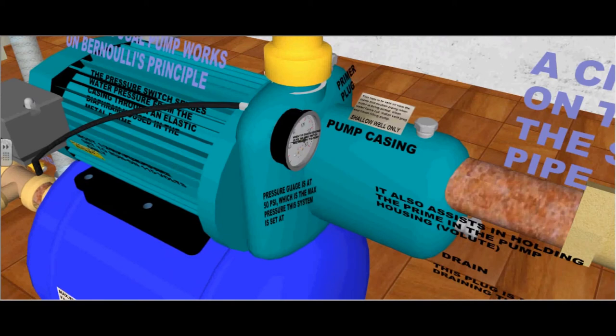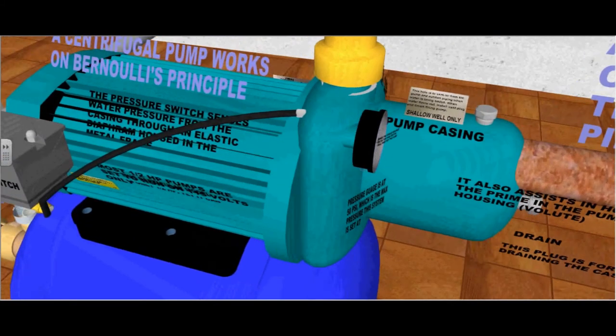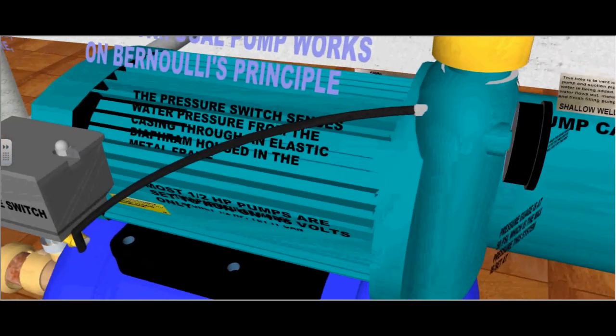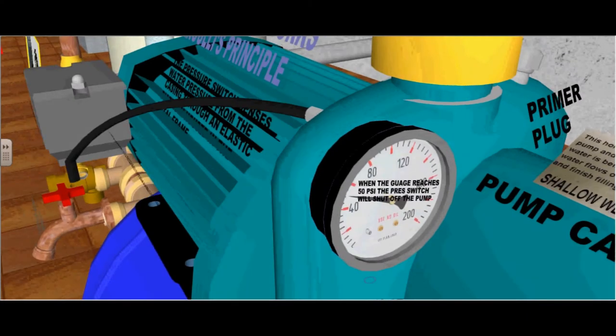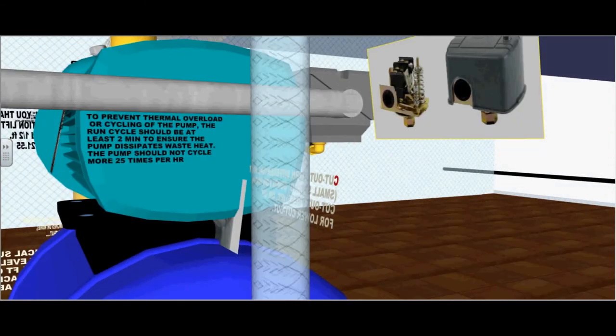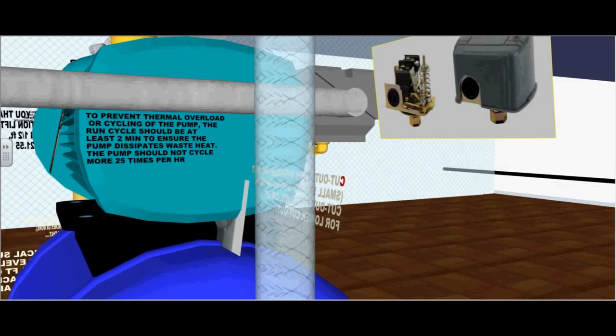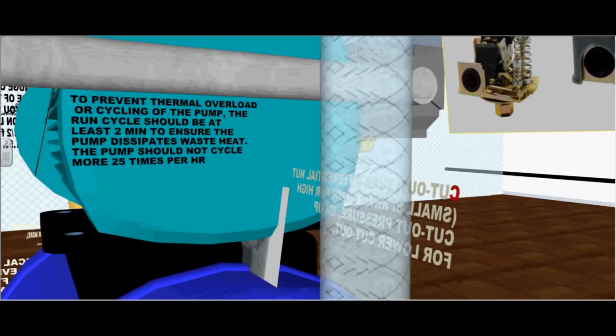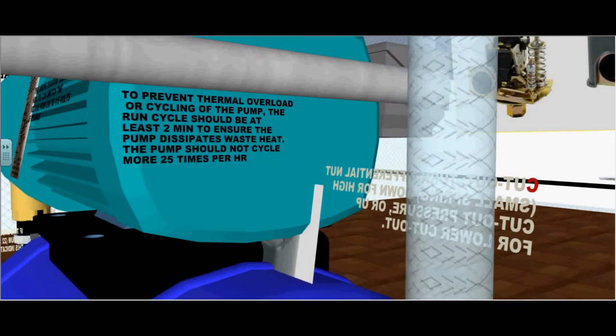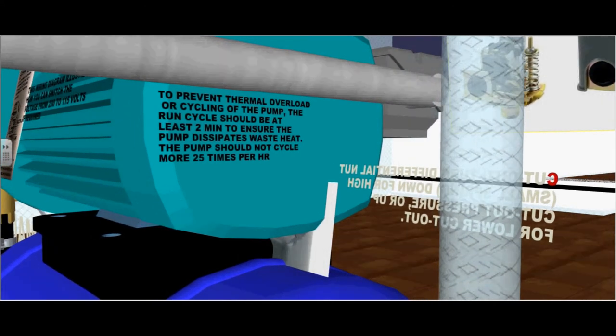This pressure switch senses water pressure from the casing through an elastic diaphragm housed in the metal frame. When the gauge reaches 50 psi, the pressure switch should shut the pump off. To prevent thermal overload or cycling of the pump, the run cycle should be at least 2 minutes to ensure the pump dissipates the waste heat. The pump should not cycle more than 25 times per hour.